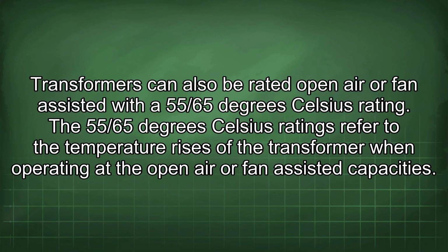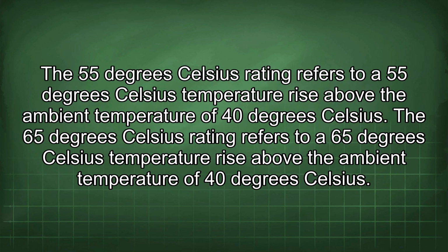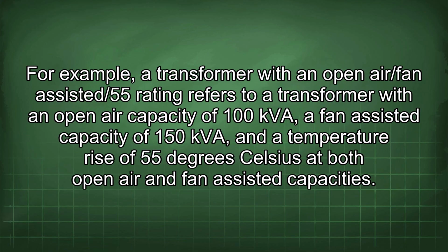Transformers can also be rated open-air or fan-assisted with a 55/65 degrees Celsius rating. The 55/65 degrees Celsius ratings refer to the temperature rises of the transformer when operating at the open-air or fan-assisted capacities. The 55 degrees Celsius rating refers to a 55 degrees Celsius temperature rise above the ambient temperature of 40 degrees Celsius. The 65 degrees Celsius rating refers to a 65 degrees Celsius temperature rise above the ambient temperature of 40 degrees Celsius.